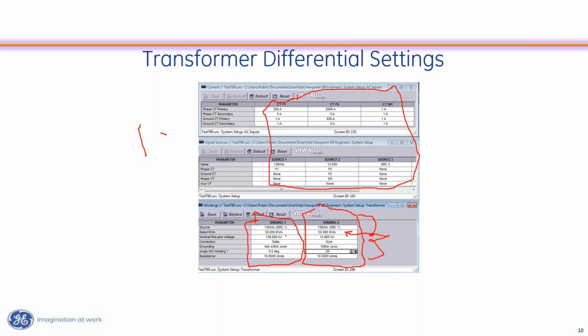The ones that really start to matter are these settings right here, the winding voltage. Now, when it says the nominal phase-to-phase voltage of that winding, for that 138 kV to 13 kV transformer, that's 138, 13.8. Now, the relay will use that nominal voltage to calculate a magnitude compensation factor. So in this case, that magnitude compensation factor is going to be 10, right? So 138 divided by 13.8 kV, that's 10.